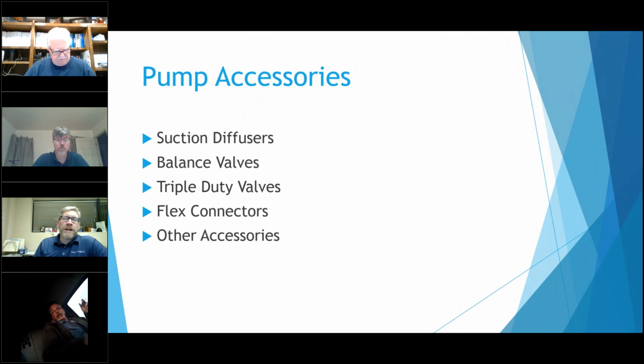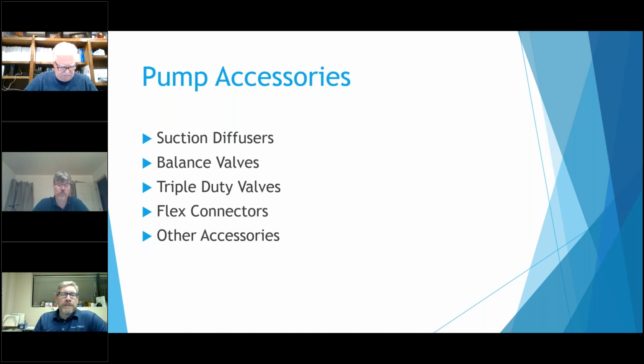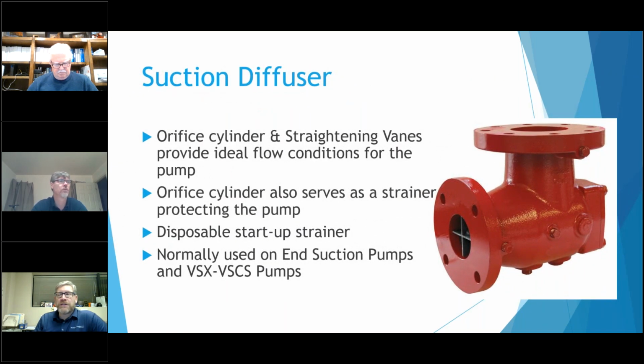Once you've gone through picking the right pump, you go to pick some of the pump accessories. Those include suction diffusers, balance valves or triple duty valves, which are very similar except for a little bit of added application on the triple duty valve, flex connectors, and a variety of other things that can go with a pump or make pump installations a little bit easier. I'll touch on some of those. The first one here is the suction diffuser. It's used on a lot of end suction pumps out there. Very few times do I not see one on an end suction pump.